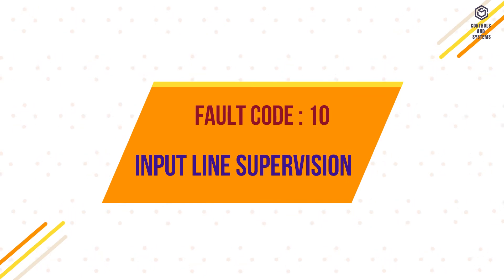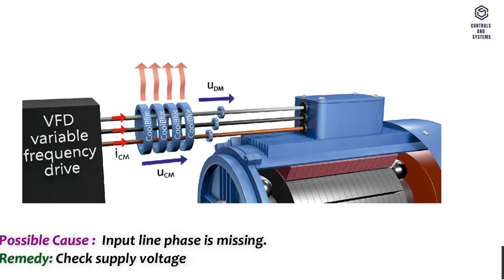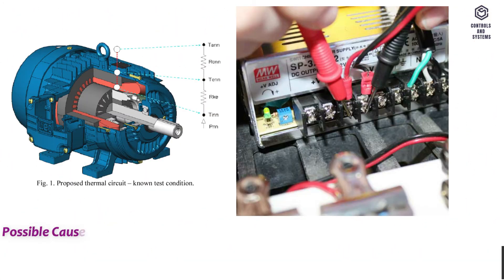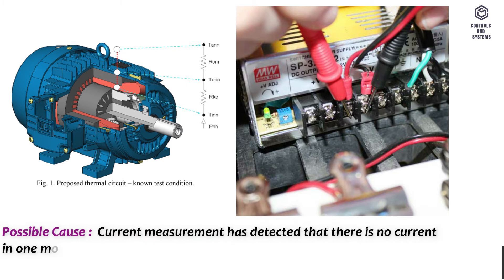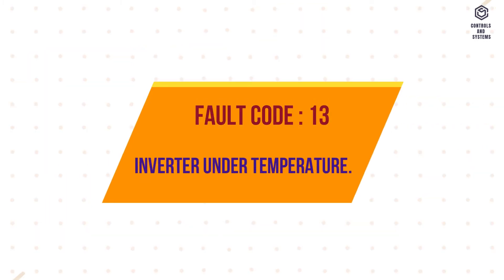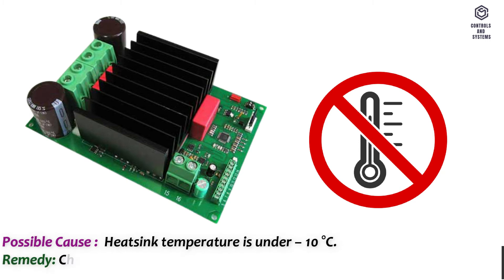Fault code 10 – Input line supervision. Possible cause: input line phase is missing. Remedy: check supply voltage and cable. Fault code 11 – Output phase supervision. Possible cause: current measurement has detected no current in one motor phase. Remedy: check motor cables and motor. Fault code 13 – Inverter under temperature. Possible cause: heat sink temperature is under minus 10 degrees Celsius. Remedy: check that the inverter is operated under specified conditions.